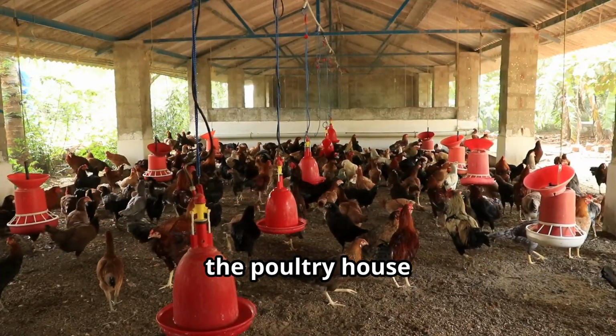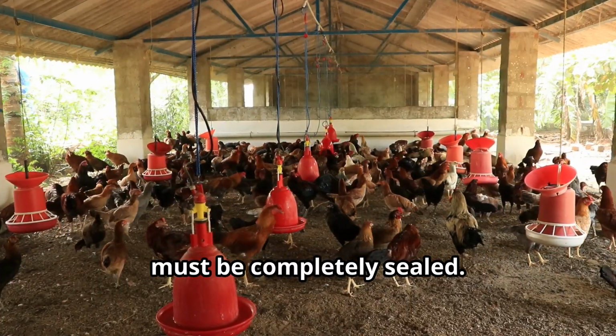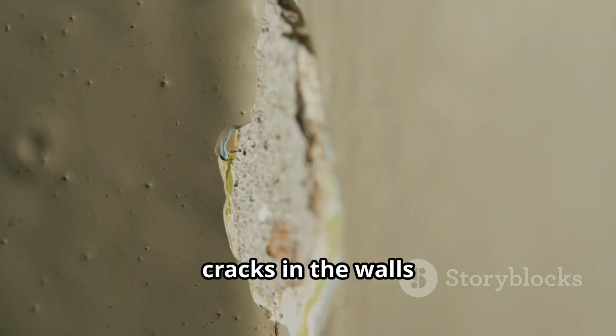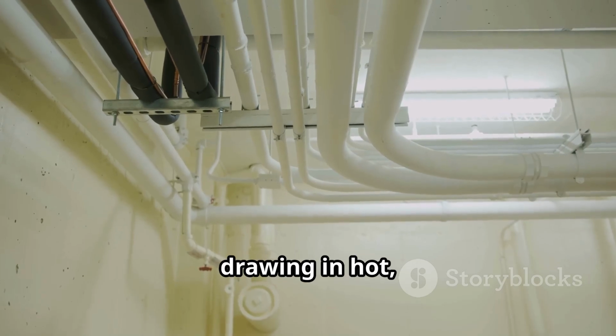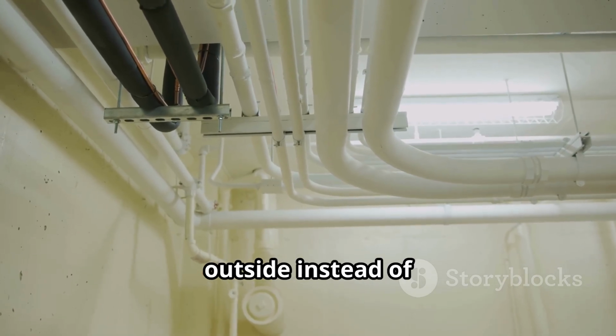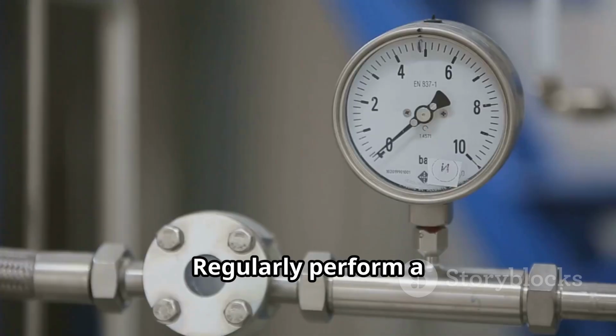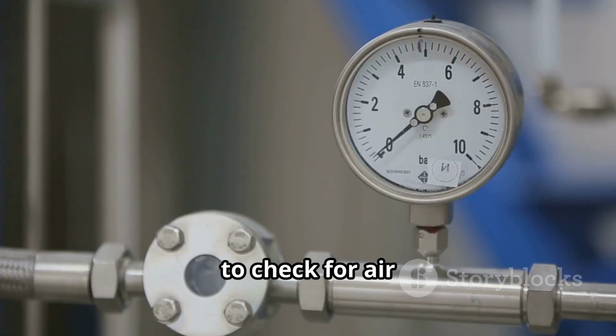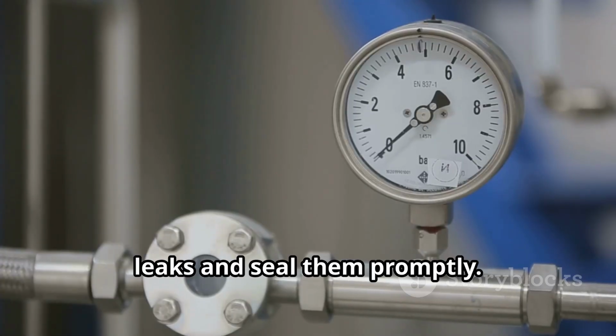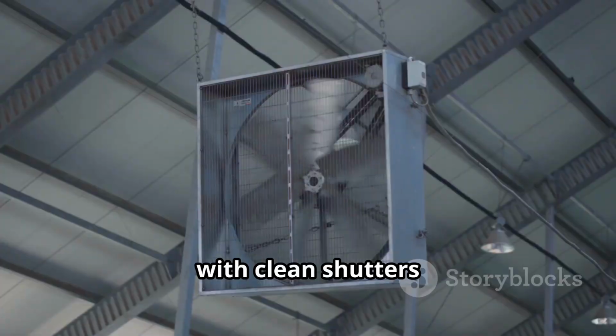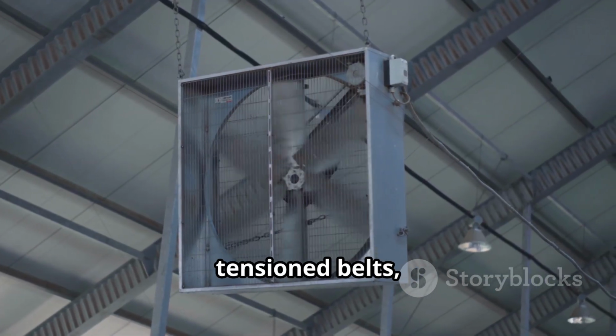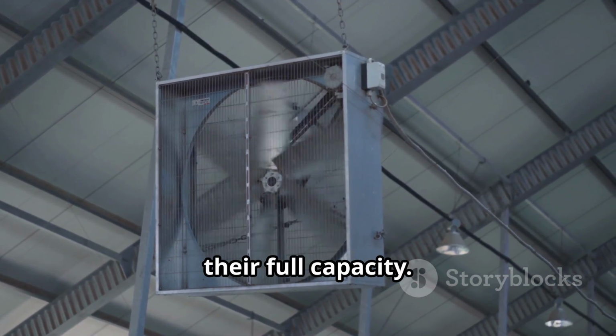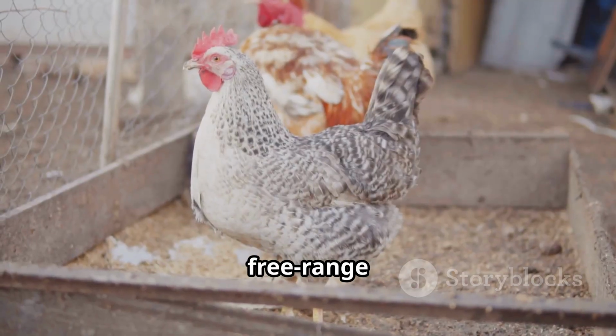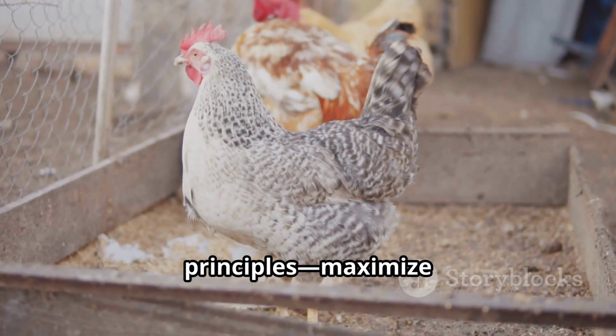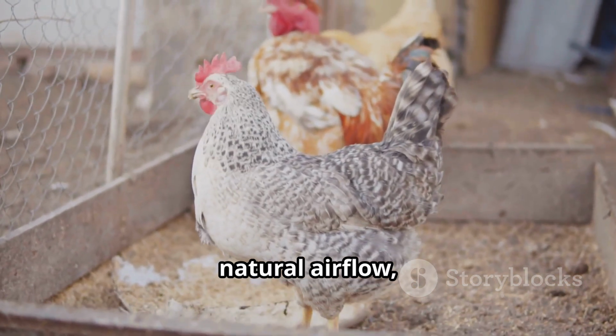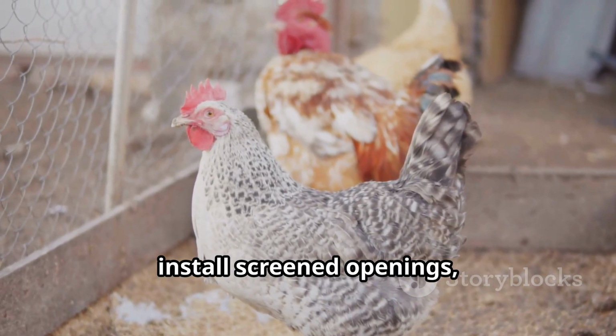For this system to work, the poultry house must be completely sealed. Any leaks from curtains, doors, or cracks in the walls will short-circuit the airflow, drawing in hot, humid air from outside instead of cool air through the pads. Regularly perform a static pressure test to check for air leaks and seal them promptly. Ensure your fans are well maintained, with clean shutters and properly tensioned belts, to guarantee they are operating at their full capacity.